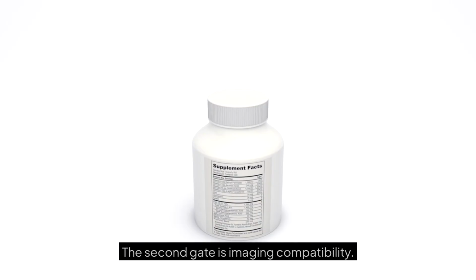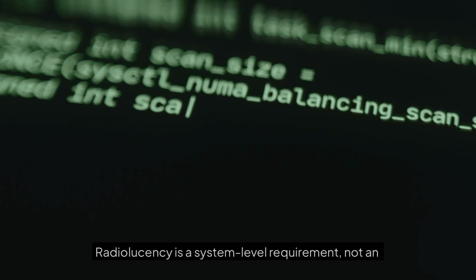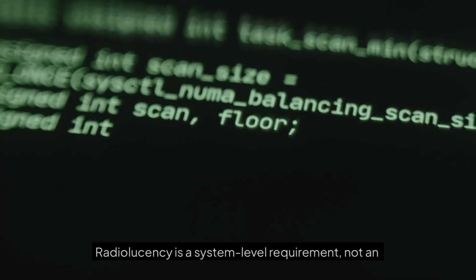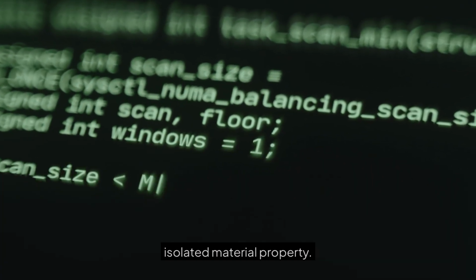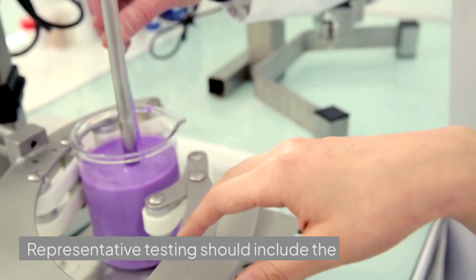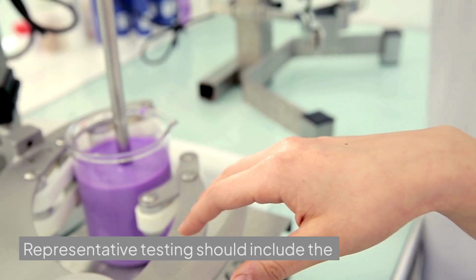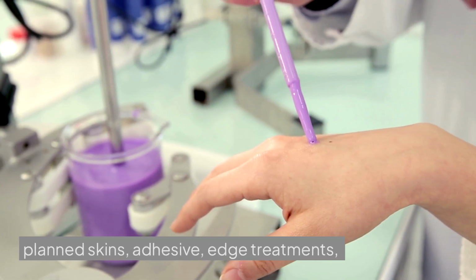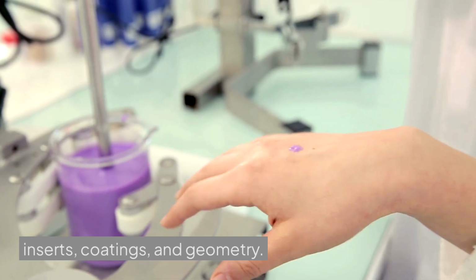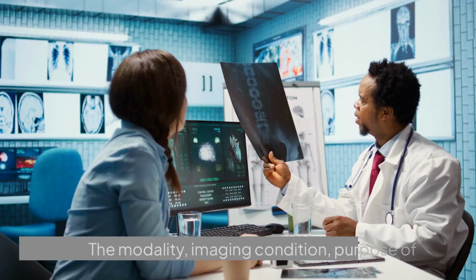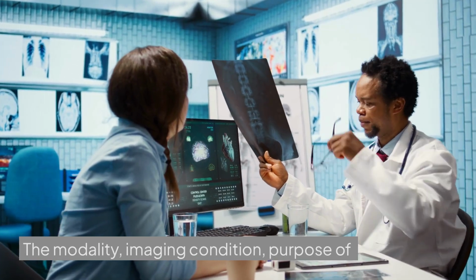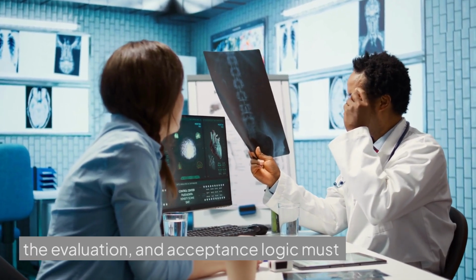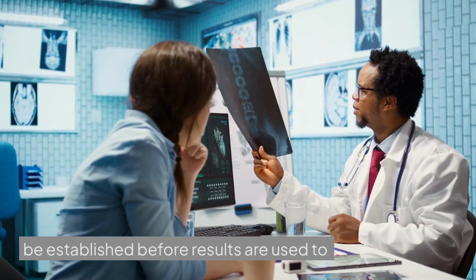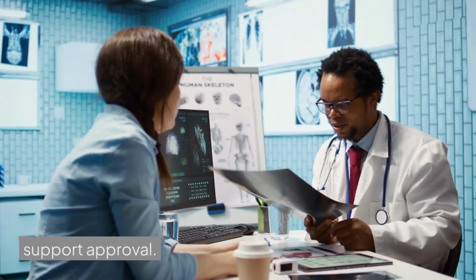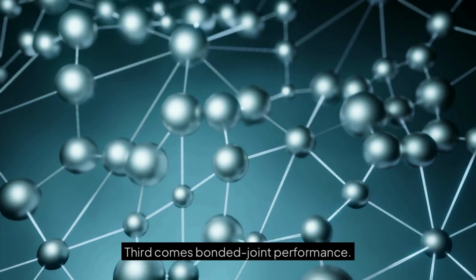The second gate is imaging compatibility. Radiolucency is a system-level requirement, not an isolated material property. Representative testing should include the planned skins, adhesive, edge treatments, inserts, coatings, and geometry. The modality, imaging condition, purpose of the evaluation, and acceptance logic must be established before results are used to support approval.